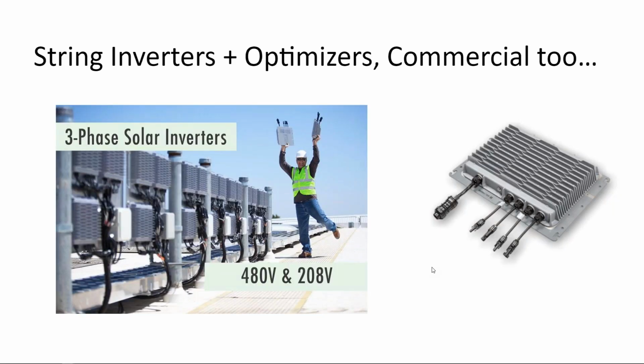Okay, so what we're looking at now in commercial rooftops is rapid shutdown requirements that require the array perimeter to de-energize during a power outage. And so, primarily now you're going to be putting these little rooftop optimizer boxes along the edge of the array.